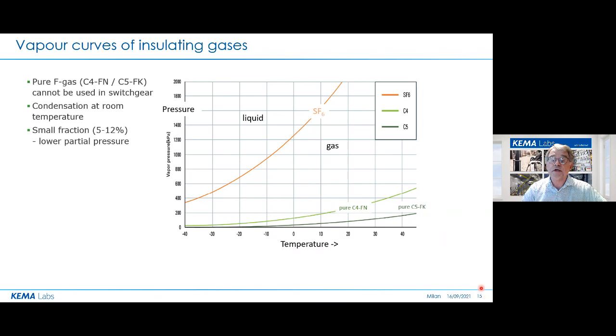The trick is reducing the pressure of the F gas. The F gas can operate under a much lower partial pressure and needs a large portion of a buffer gas, CO2, at a much higher partial pressure for dielectric capability. This is why only a small portion of F gas can be allowed inside. And because in high voltage switchgear the pressure needs to be higher than in medium voltage, we can see that a difference is there.